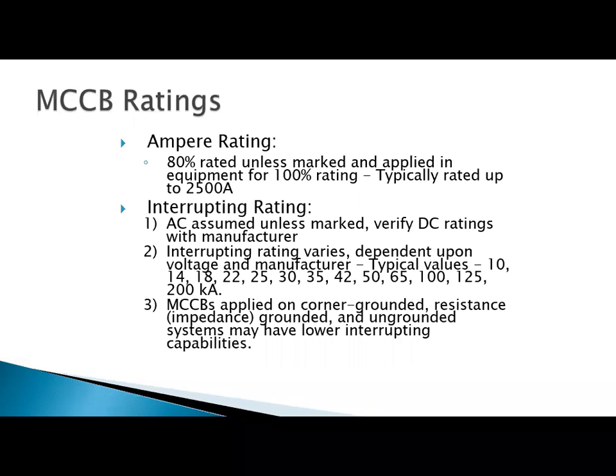And so on the side of my breaker, if it is a molded case breaker, I am going to have what they call an IR rating. We used to call it AIC. Now it's IR. And it is going to be marked. And for residential applications, that interrupting rating is going to be 10,000 amps. So in a residential situation, my circuit breaker can safely interrupt 10,000 amps, which is pretty good because the short circuit current would never really get above this number in a residential application.